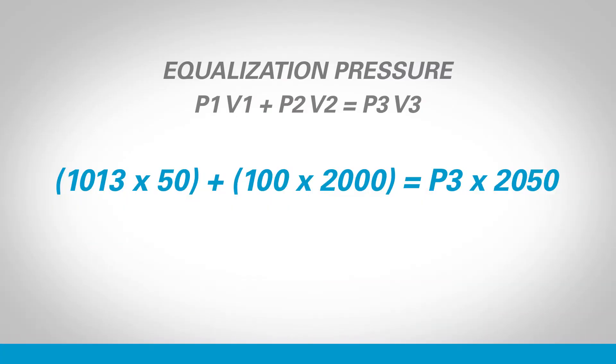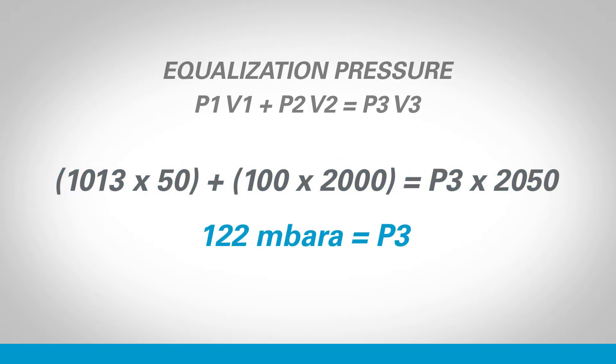So if our process chamber is 50 litres vented to atmosphere and the vacuum tank is 2,000 litres held at 100 millibar absolute, we can very quickly calculate what the equalization pressure will be: 1,013 times 50, plus 100 times 2,000, equals the total pressure multiplied by 2,050. That gives an equalization pressure of 122 millibar absolute.